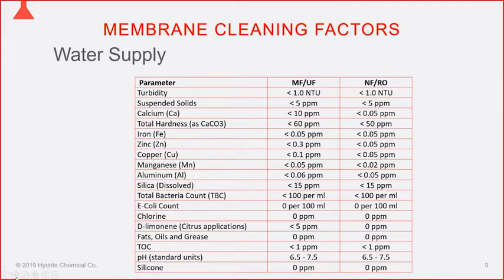If food processing defoamers — not CIP defoamers like Defoamer 553 — are silicone-based, it's very important to keep those away from membranes. A silicone film from a defoamer on a membrane is very difficult if not impossible to remove, causing major headaches. The other parameters on the chart are mainly dissolved minerals. For polished COW water or RO permeate, mineral content is generally low, but bacteria loading can be a concern — UV or chemical biocide treatment is needed.